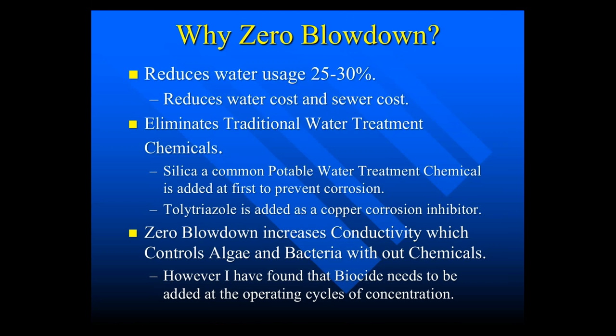Why zero blowdown? It reduces your water usage 25 to 30 percent, which saves in both water cost and eliminates traditional water treatment chemicals. Silica is used, which is commonly used in potable water systems, and tolytriazole is added as a copper corrosion inhibitor. Zero blowdown increases conductivity, which theoretically controls algae and bacteria without chemicals, but I found that biocides are still needed at the cycles of concentration that we tested.